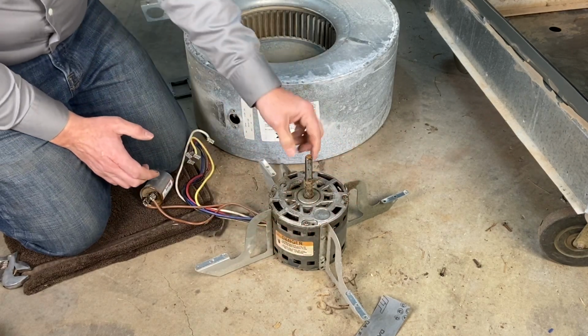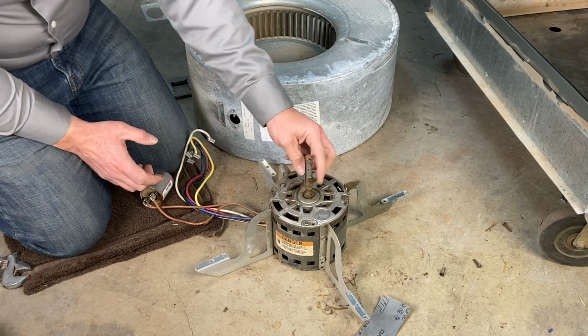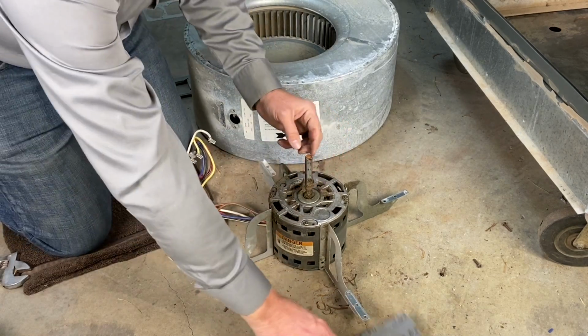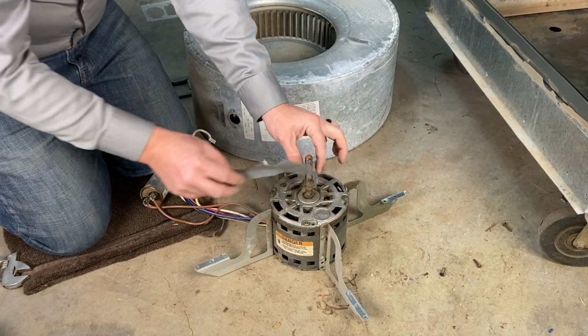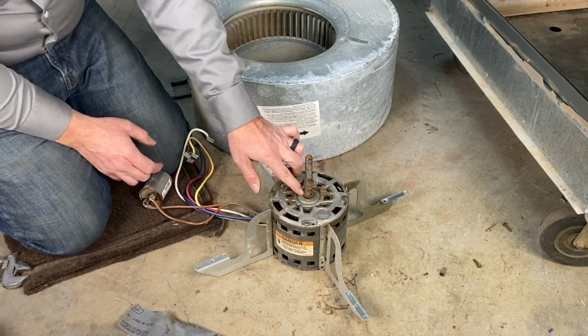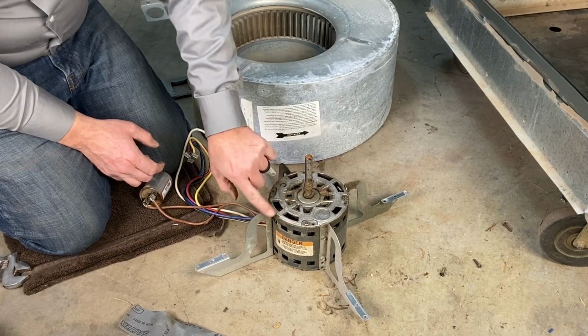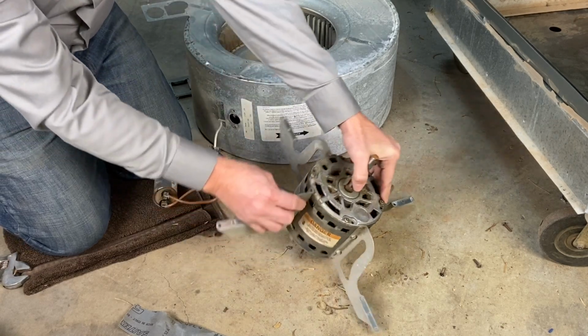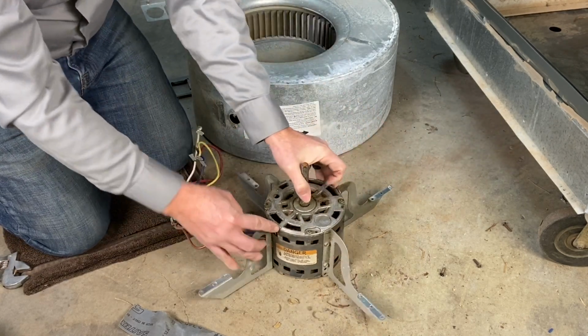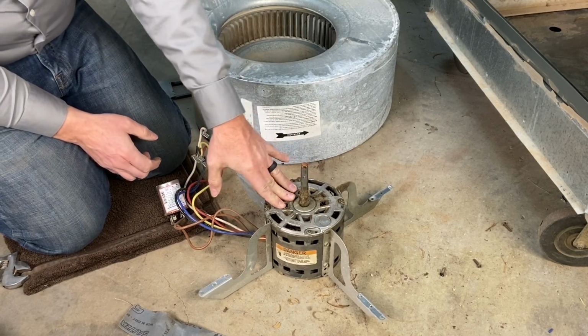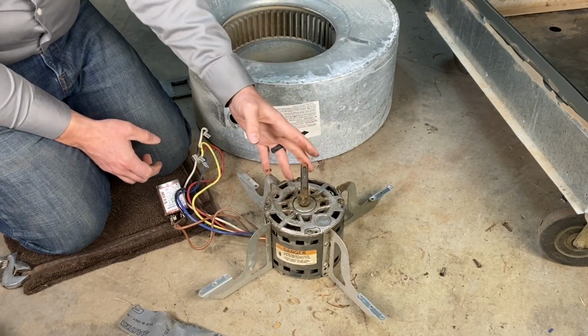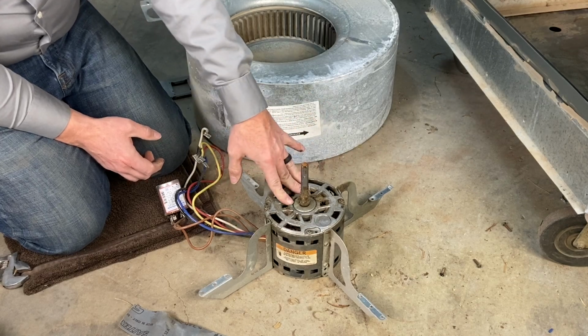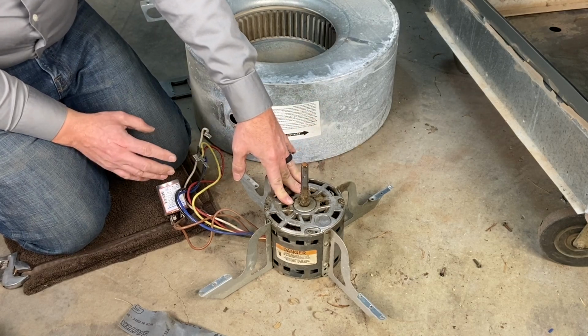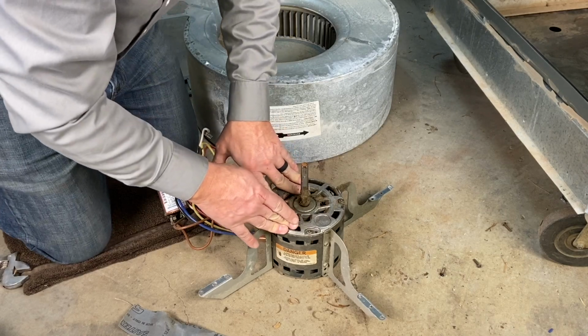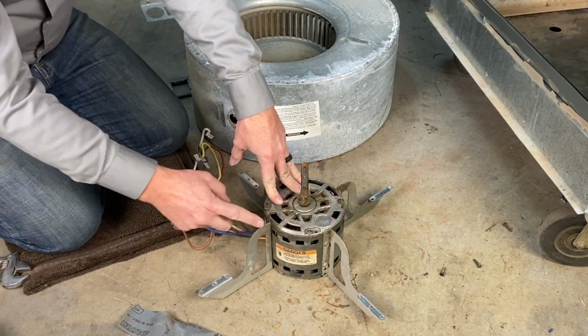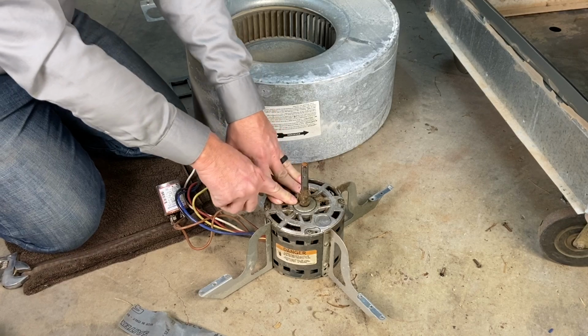If we can see, this motor here has all of this fuzz and dirt on here. What we're going to want to do is take our sand cloth and sand this shaft all the way down. The bearings right here are at the bottom, and these are sealed bearings. They have the old casings for the oil ports, but you can't oil these. They're sealed for the life of the motor. Once these bearings go bad, you have to replace the motor. Don't try oiling these, and especially don't use any kind of penetrating oil. WD-40 has a product that's used for a lot of things, but not for these motors. It'll actually push the oil that's in there out, so it causes a problem.